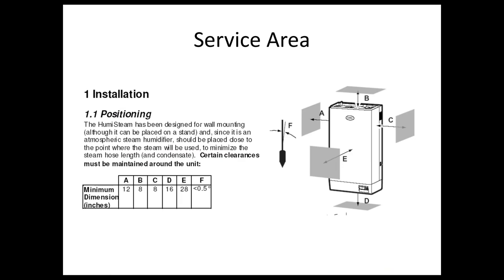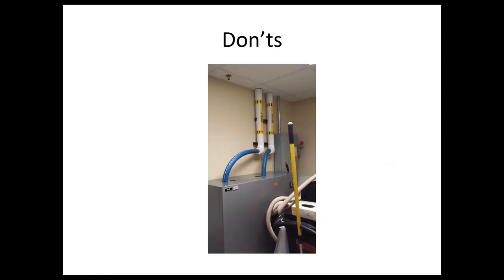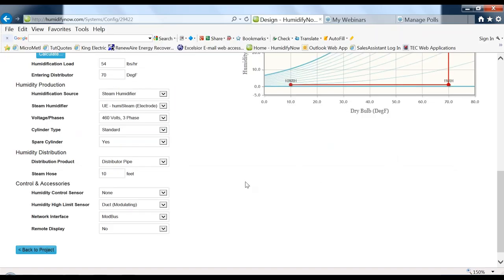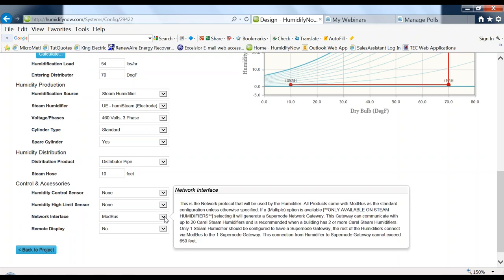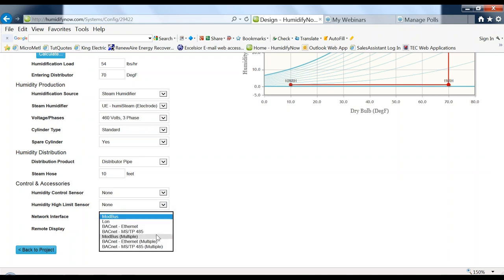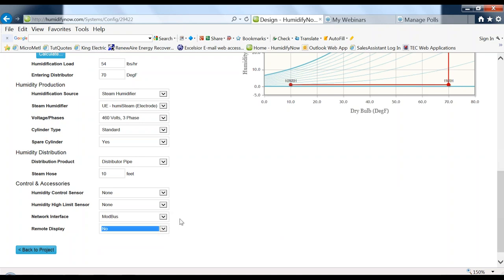Service area clearance is often overlooked. For the electrode model, you need 28 inches of clear space to pull out the steam canisters. If objects are placed in front, servicing becomes very difficult — something facilities staff will regret. For controls, you can specify various humidity sensors — duct or room mounted, modulating or on/off. Most commonly we see modulating. Carel's standard communication is Modbus, but BACnet and LonWorks controls are also available. A remote display can be specified if the unit is in a hard-to-access location.